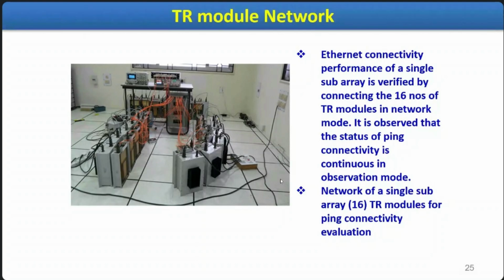Initially we put 16 TR modules into one control network, because pinging issues will be there, timeout errors will come. You have to see and clear that, because the vendor doesn't know, they simply supply an evaluation circuit in the control card. During testing time it will come up, so while operating in real time, you have to care about pinging status.